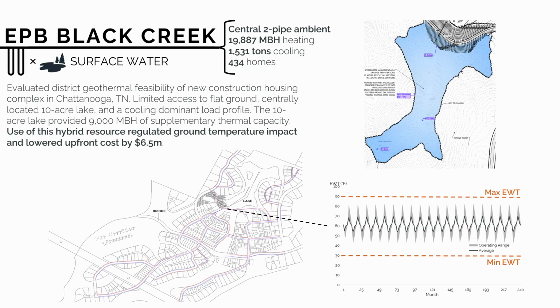And we size those. We worked with an expert, and we size those for a maximum 1/2 degree per day of temperature drift in the lake under peak conditions. And what that essentially was able to do was cut the size of the bore field in half. So half of the load is handled by the lake, half is by a bore field. The customer also has the option to do a boiler or cooling tower with the remaining load, should they choose.